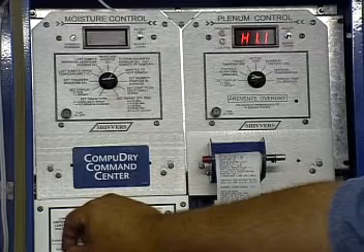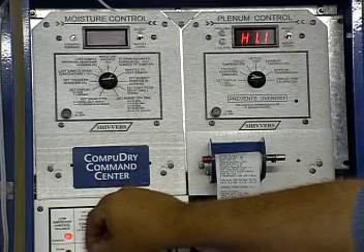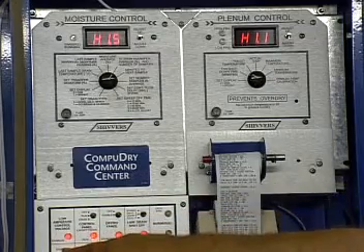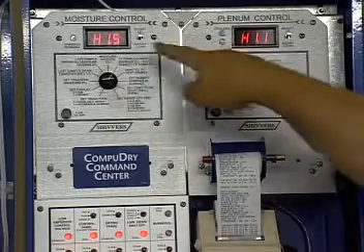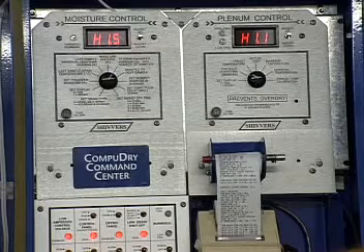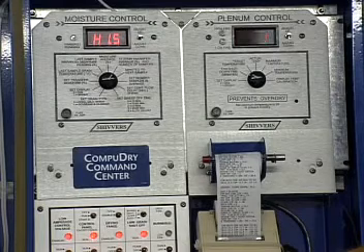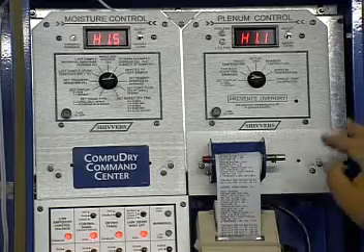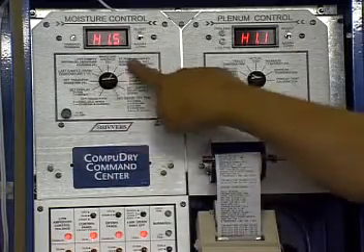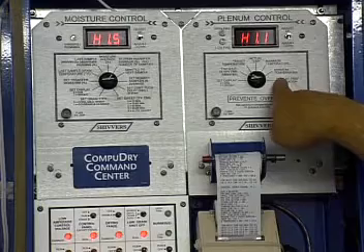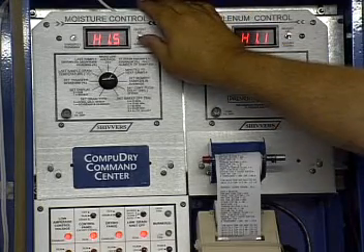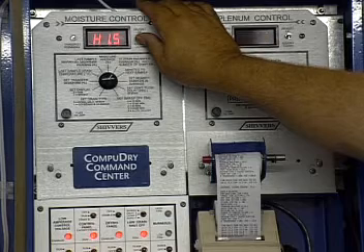Again, I just run that circulator. Again, I'd run that continuous flow auger like that. I'll put them down to automatic. Now we have both modules blinking the module number. The burner switch is still on. Physically, you have to go back and turn the fan on. Once you turn the fan on, I don't want to change any of the settings because everything is good from before. All you have to do is activate this moisture side right here, up or down till it says 888.